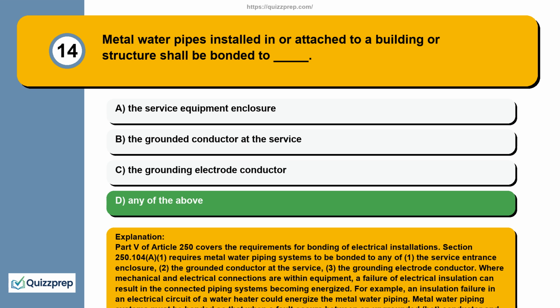Section 250.104, A.1, requires metal water piping systems to be bonded to any of 1. The service entrance enclosure, 2. The grounded conductor at the service, 3. The grounding electrode conductor. Where mechanical and electrical connections are within equipment, a failure of electrical insulation can result in the connected piping systems becoming energized. For example, an insulation failure in an electrical circuit of a water heater could energize the metal water piping.